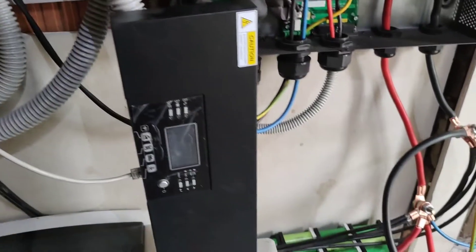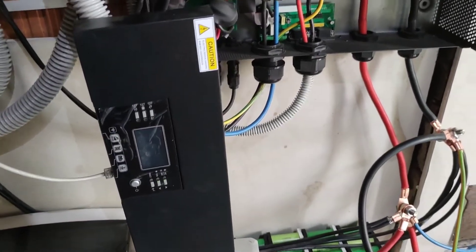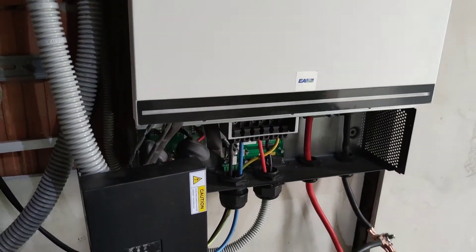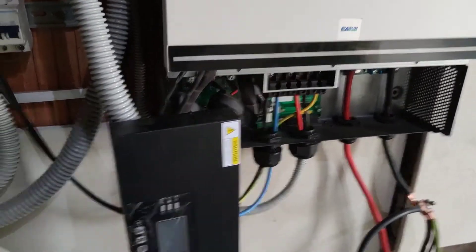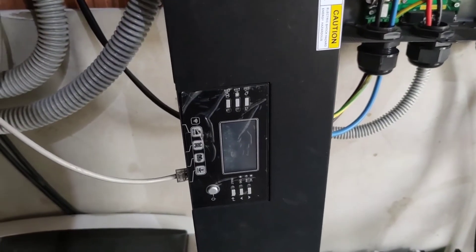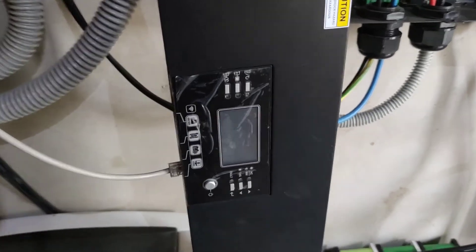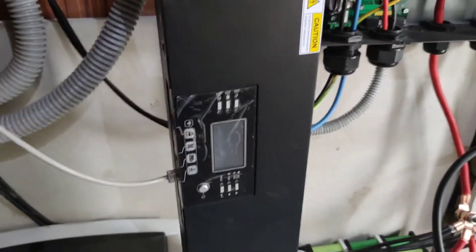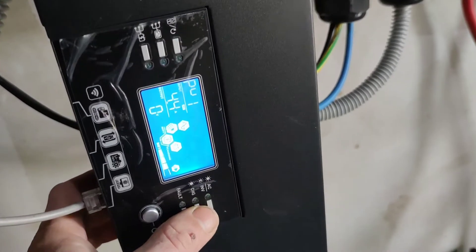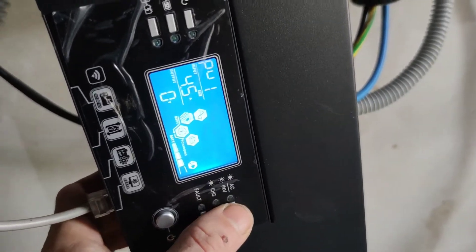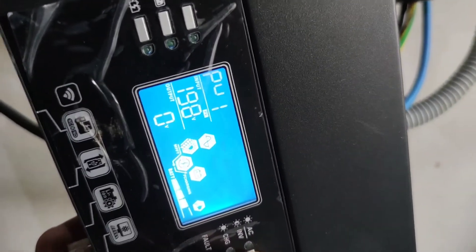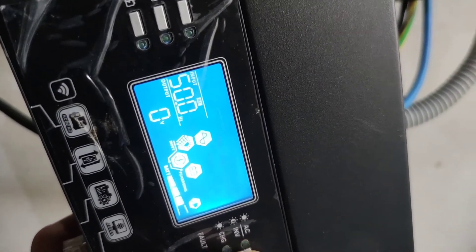One more thing that I just realized with this 8 kilowatt Easun inverter is that even though it's shut off at the moment, it will still produce 230 volts on the output when the input is applied.